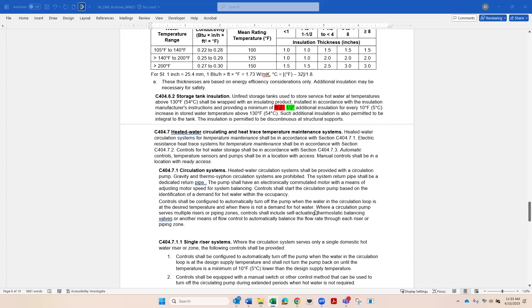Nobody in the piping industry or the tank industry calls out an R value. I propose a half inch. The reason you don't use R values on pipe is because it's based on the temperature inside the pipe and what you want the surface to be at. Our tank values are all based off 70 or 75 degrees. But in tank or pipe insulation, do we have 120-degree water? 140-degree water? 160-degree water? That's why we use thickness, and we use a K factor based on that. Our charts have gone to that, and thankfully, that's the way the industry is.